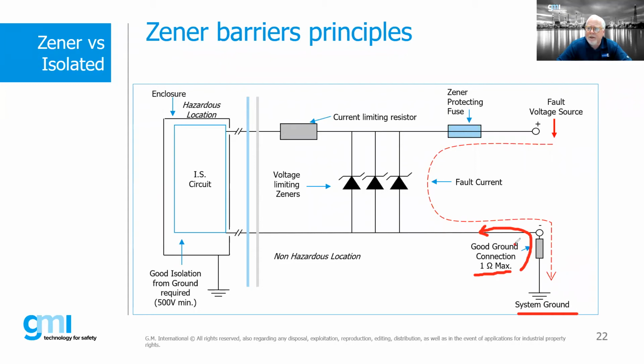Also, if we don't make this connection, we could have a fault condition that travels down this leg and causes a problem there. So there are some very key important things to remember when using Zener diode barriers that we have to keep in mind.